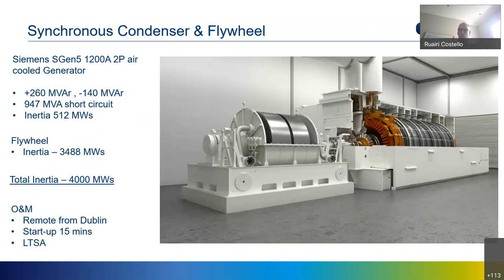So this is the best picture we have to date from Siemens of what it will look like. You see the generator motor on the right and the flywheel on the left. It's a Siemens SGen 5 1200A two-pole machine. It's air-cooled. It's a well-proven generator in thermal applications, and has many references as a synchronous condenser also. It's got a reactive power range of plus 260 megavars into the system, and it can absorb 140 megavars from the system. It can also contribute 947 MVA of short circuit.